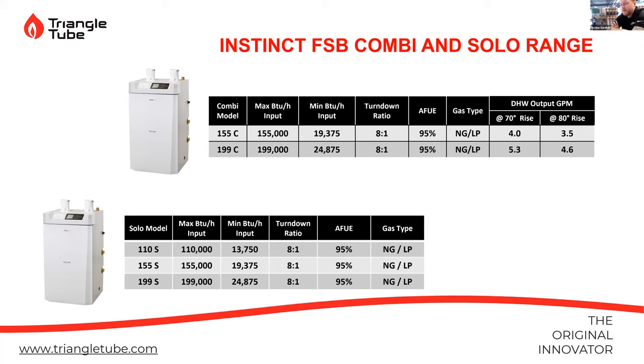So new to our line is the floor boilers. This is really where I see a lot of advantage. I see a lot of the market going this way, where wall boilers, we had these come out in our market because over in Europe, they're doing wall boilers and they mount in the kitchen, their cabinet depth, and they fit in there nice and tight. Everything's crammed in there. Well, I think we're finally, in the past 5-6 years, realizing that we have basements and we have much more room. So we're looking at ways to save money on install, save time, because manpower is a big thing as well. So if we don't have to build a wall, and we can mount or just set a boiler on the floor, it's a great way to go and we can save that time.